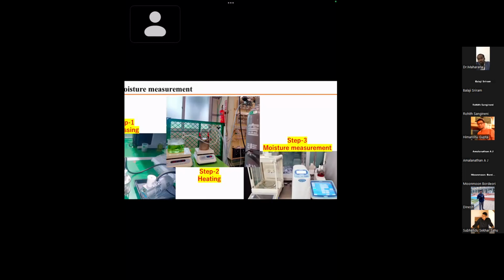So according to our requirement, suppose I need to measure the breakdown voltage or partial discharge inception voltage at 100 ppm actual moisture. I need to stop it there. Suppose we need to check the ppm every 10 minutes. It may not be exact. Sometimes in the practical scenario it is very tedious. Let's say you check and it is 79, and maybe after 5 minutes it crosses 100. So we need to be very careful.